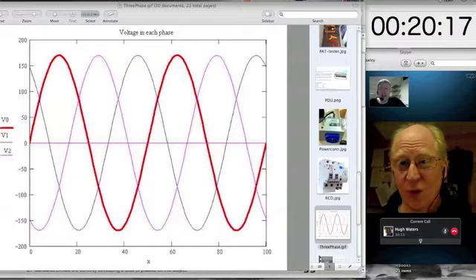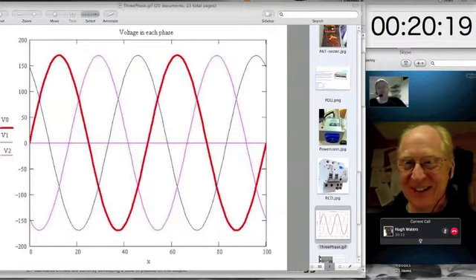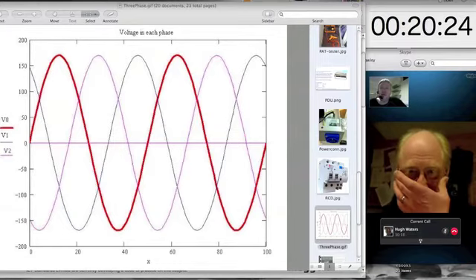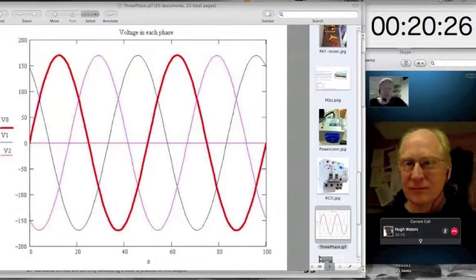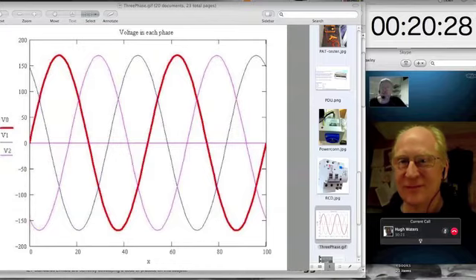So, yeah, indeed. There was a studio I worked at in St John's Wood in the early 90s, and at one point, because the MD thought that the electricity bill was very large, I was tasked to find out why. And putting a clamp meter on the 3 incoming phases in the lines room, I discovered that we were pulling about 150 amps on the red phase, 20 amps on the blue phase, and only a few amps on the yellow phase. And of course, we were paying as if we were consuming a constant 450 amps, which was more than twice what we were really using.